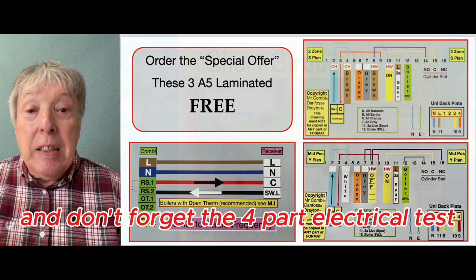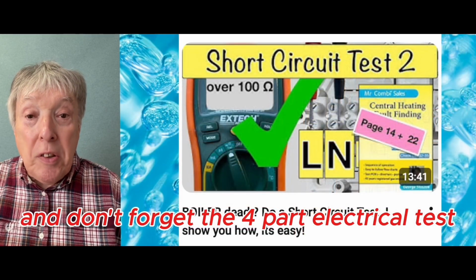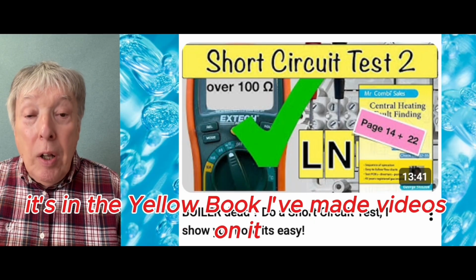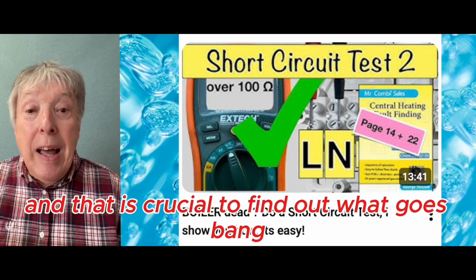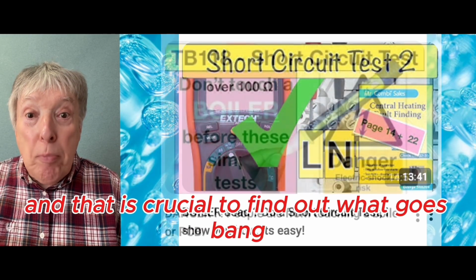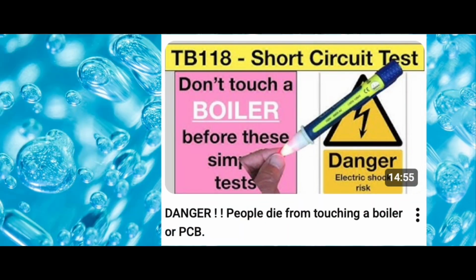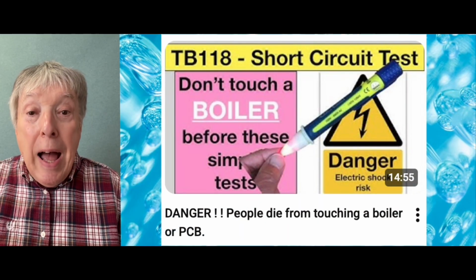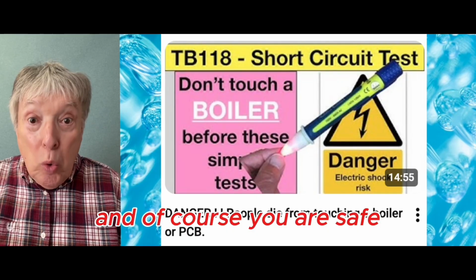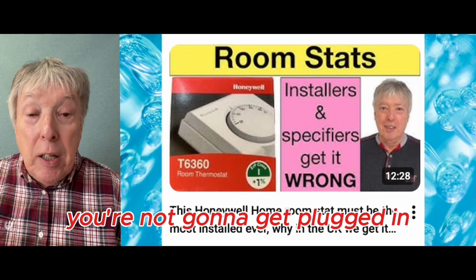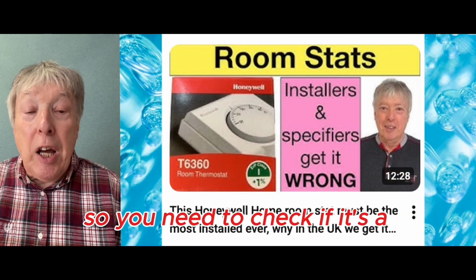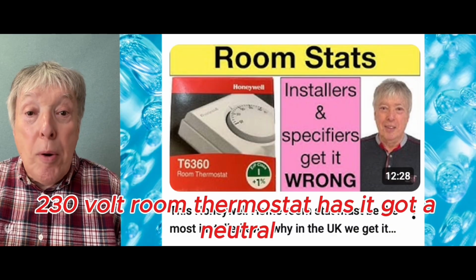And don't forget the 4-part electrical test. It's in the yellow book. I've made videos on it, and that is crucial to find out what goes bang. So make sure that the boiler and the customer, and of course you, are safe. You're not going to get plugged in. So you need to check if it's a 230-volt room thermostat.